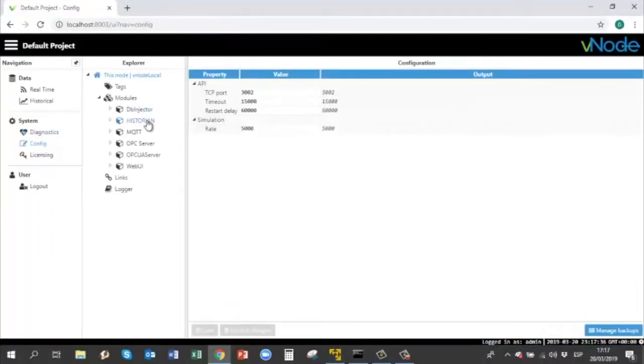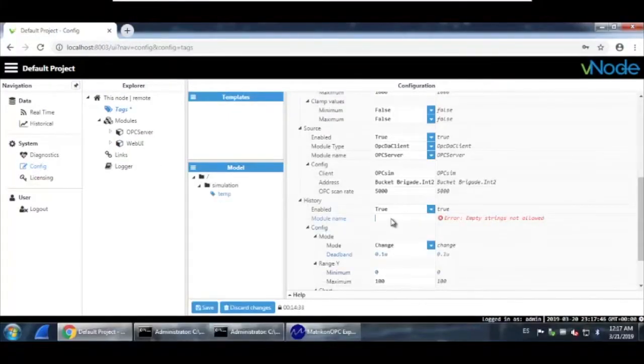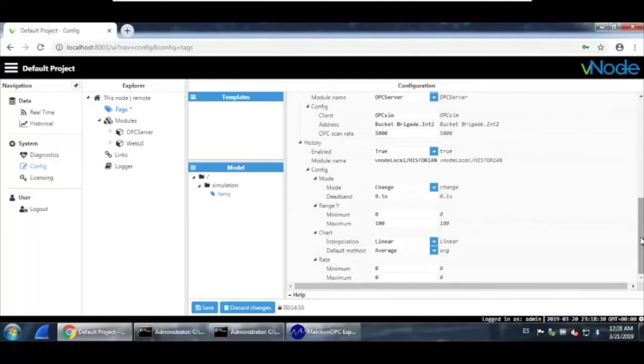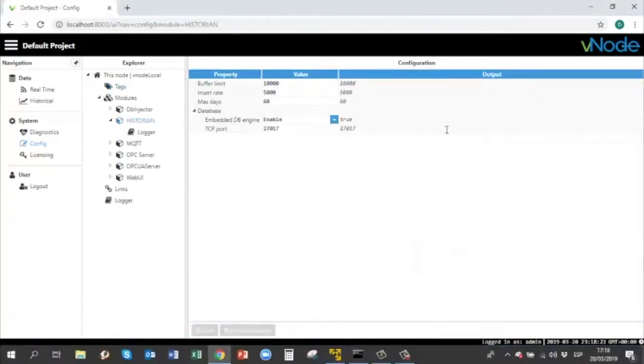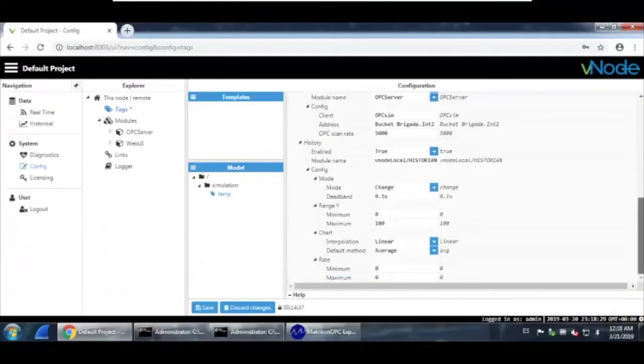Under history, let's set enable to true. The module name refers to which historian module this tag belongs to — in this case it will point to the historian created on Vnode local. Remember we already created a historian module named 'historian'. We must type the link name — 'connection' — followed by a backslash and the same name as the module created on Vnode local, which is 'historian'. This will make the tag log into the MongoDB embedded on Vnode local. Hit save.